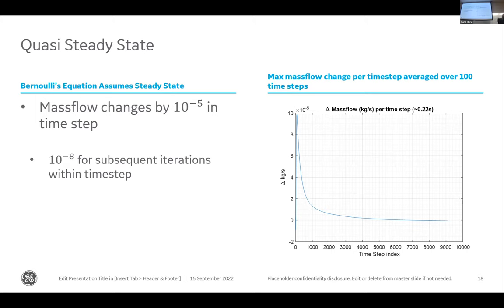Because this is such a slow-moving system, our time steps are about 0.2–0.25 seconds. For any given time step, mass flow is essentially constant, with very little change. When we do have changes in things like Reynolds number, we solve for those K values and fitting losses based on Reynolds number so that we take into account any actual changes.